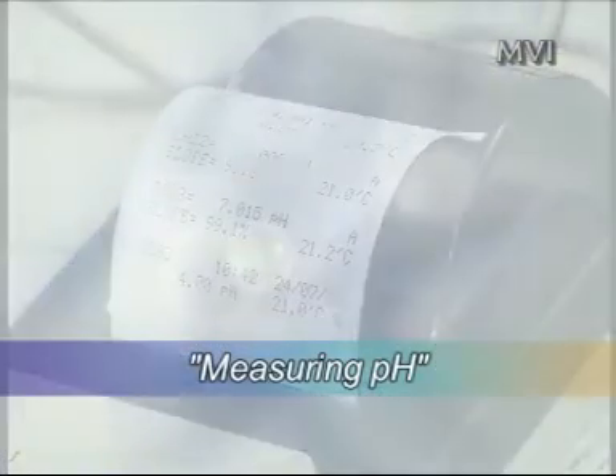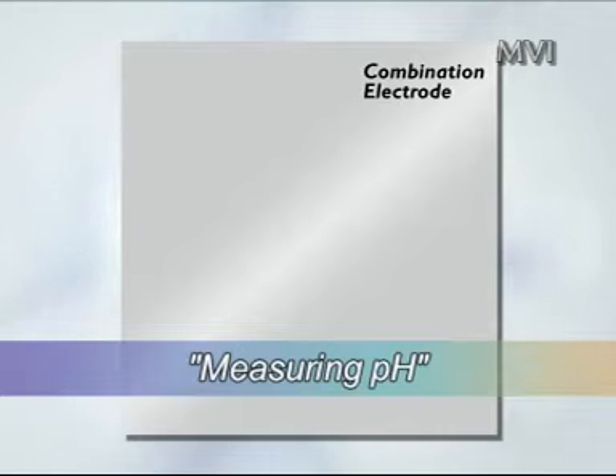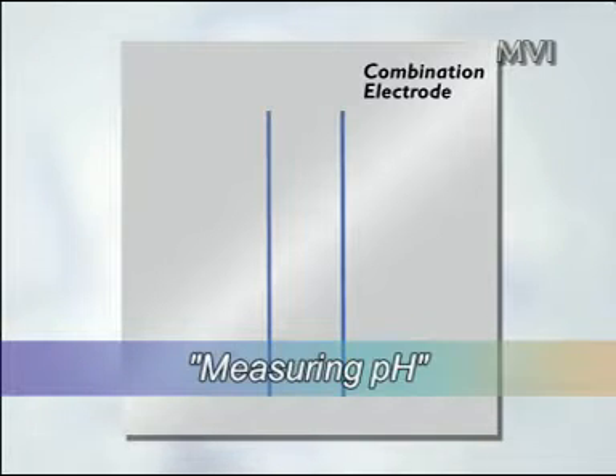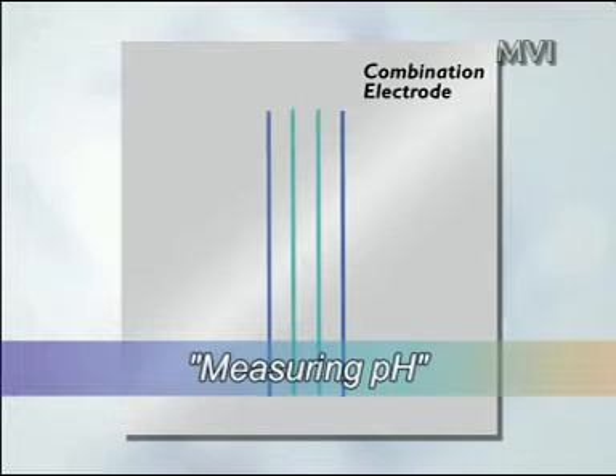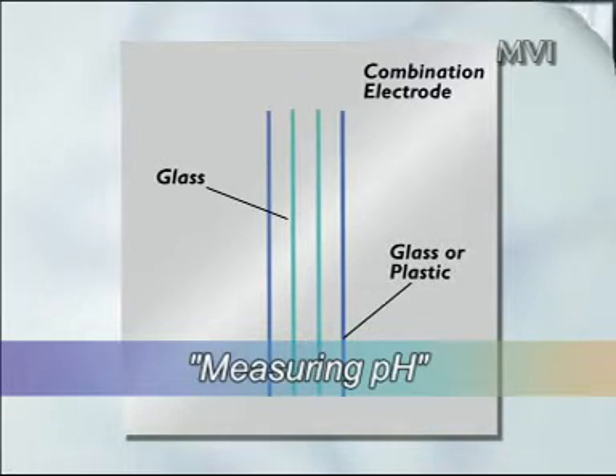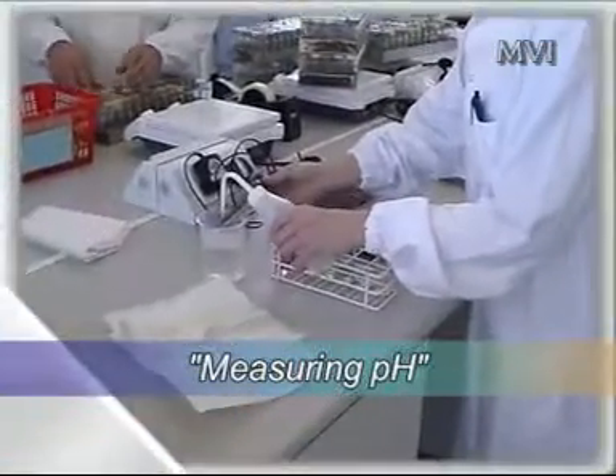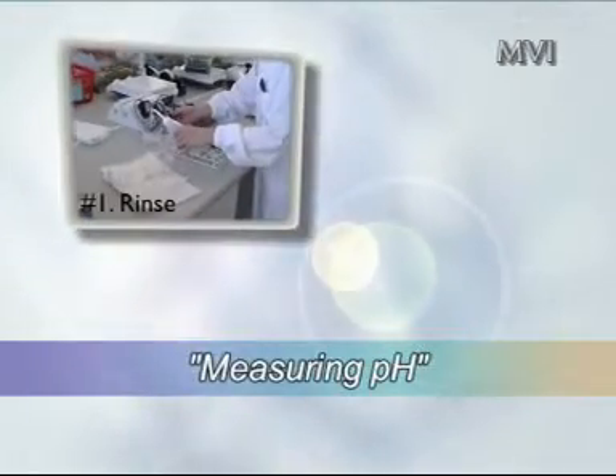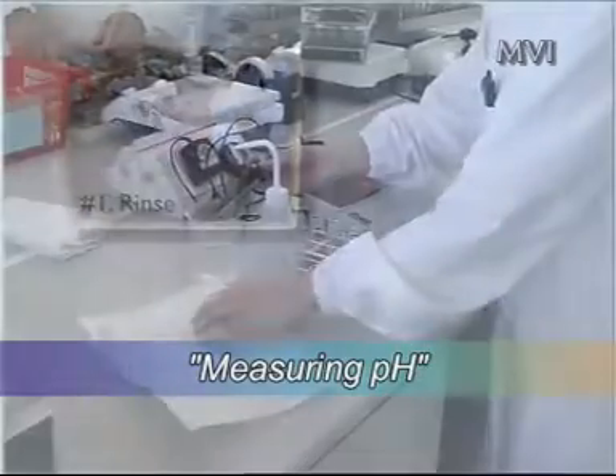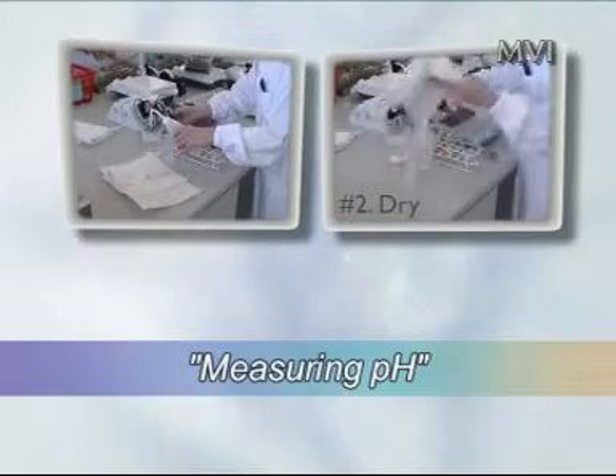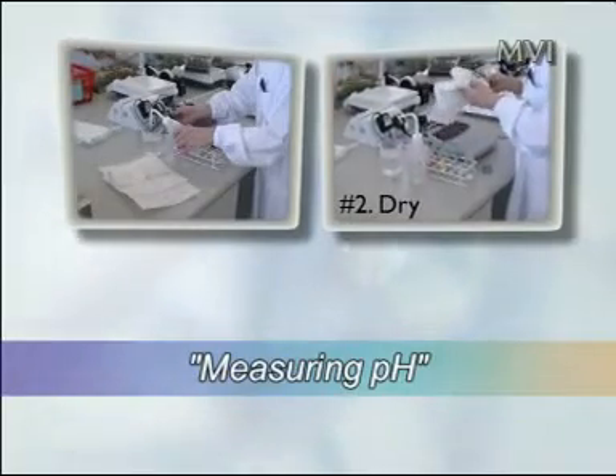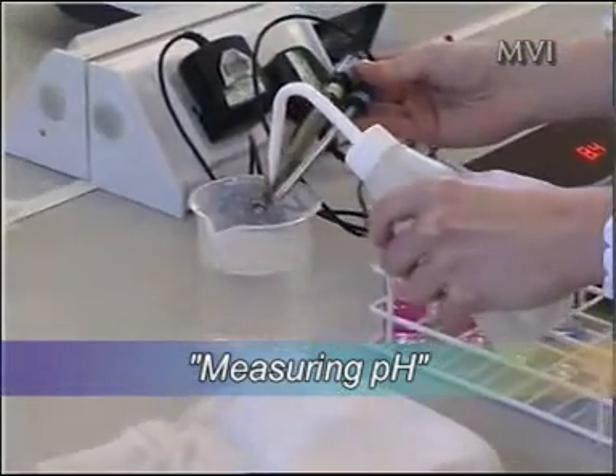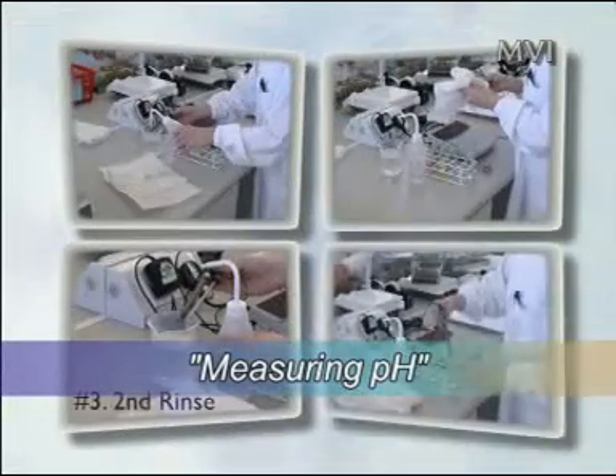Most modern probes are of a type called combination electrodes and can be quite complicated. Basically, the probe consists of two concentric tubes, the inner tube made from glass, the outer one made either of glass or plastic. An ion-sensitive electrode could hardly be more simple. First, rinse the probe with distilled or deionized water to remove any traces of previous contact materials. Second, blot it dry with a clean tissue. Third, rinse again. And fourth, immerse it straight into the solution you want to measure.